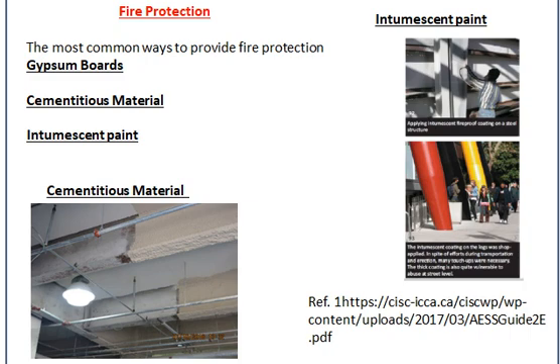Cementitious materials are sprayed over the steel members. There are three checks which should be carried out to verify the material is in good condition: the first test is adhesion of the cementitious material to the steel member; the second test is the thickness of the material; and the third test is the density of the material, which verifies that the components were mixed correctly and gave the right density as per the manufacturer.